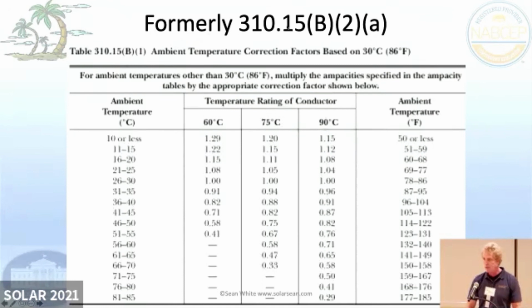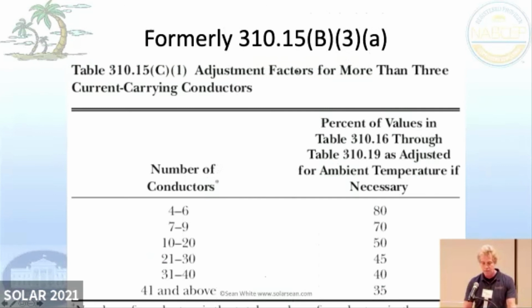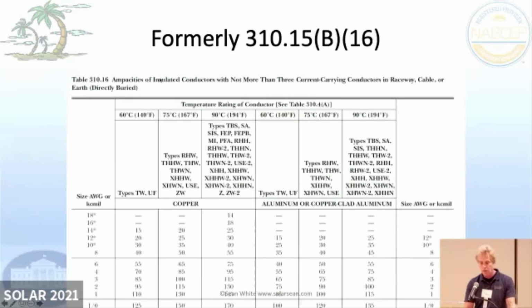But they changed it, just to make it more difficult, from 310.15(B)(2)(a) to 310.15(B)(1). That's all that's different. And they changed 310.15(B)(3)(a). That's derating if I had more than 3 current carrying conductors, because of conduit fill. If I had 4, then I can only carry 80% of the current, so we're derating that wire by 0.8. And they changed that to 310.15(C)(1). Then this one is even more crazy because it used to be called 310.16. Then for a few code cycles they called it 310.15(B)(16). And now they've changed it back to 310.16. So at least it's easier to remember because that's what it used to be called.